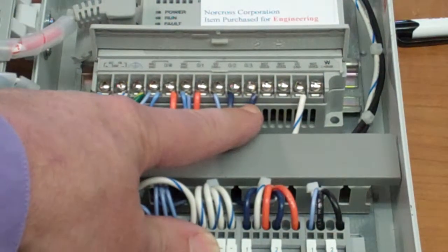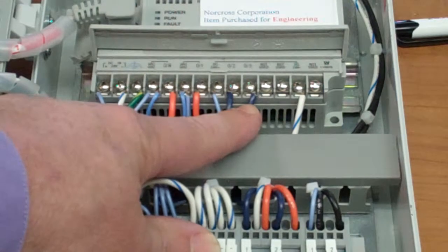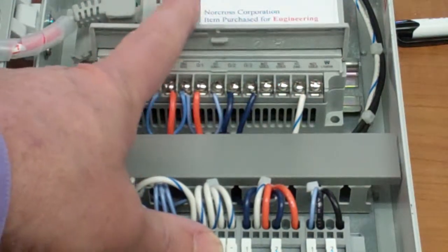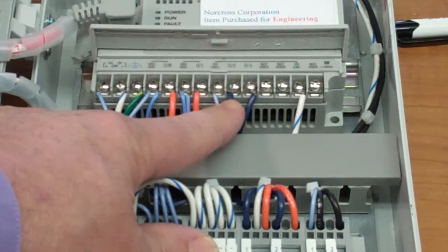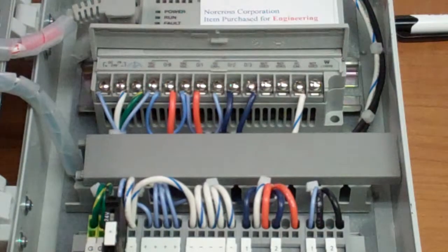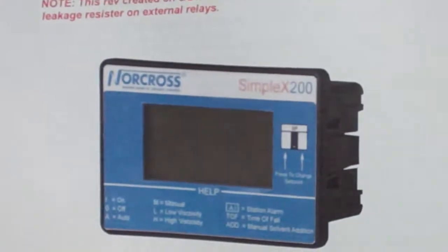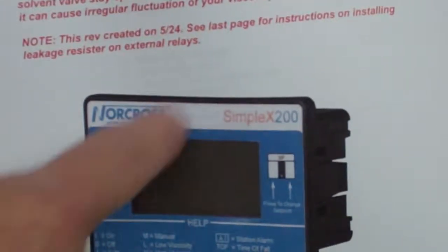We have a number of customers who got these in the field before we realized the phenomena. And we had a call recently, a customer says, hey, when I turn the power on to this air valve output is always on. The air valve's always on. This happens to be in our simplex line. So before you push the touch panel on the simplex to start the station, the air valve is on.